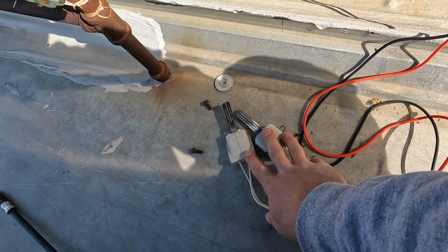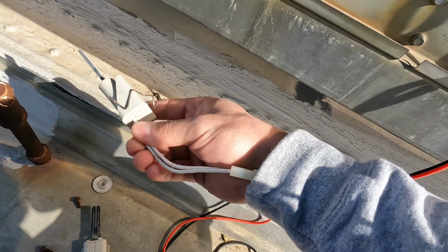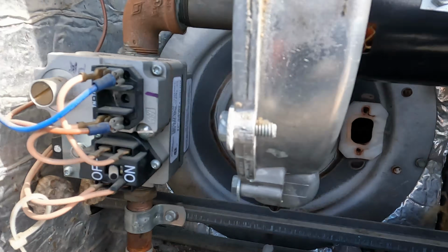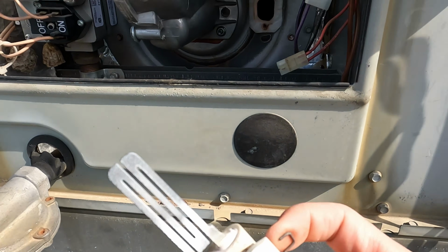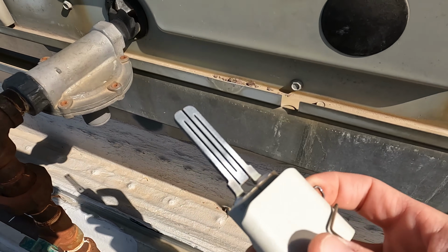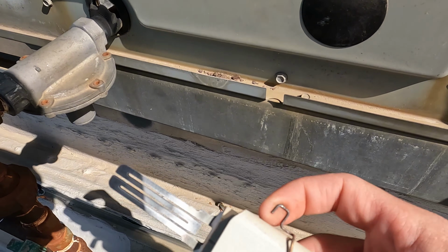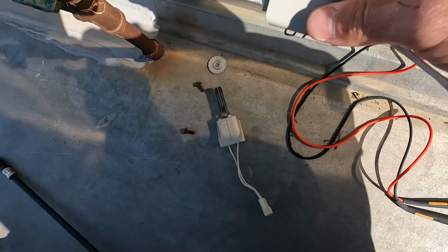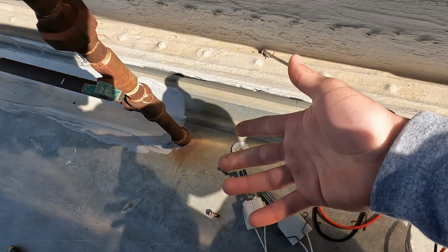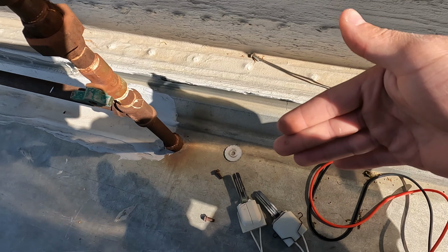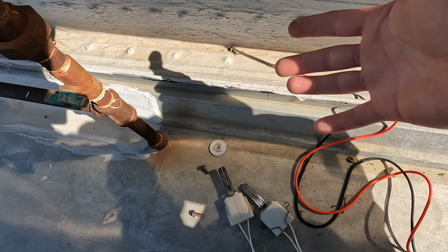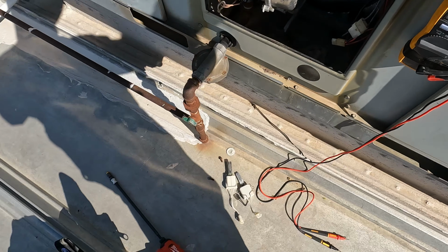So with both of these testing good, they also act as flame rectification. As you can see, there's no flame sensor in here. So with them being dirty, I guess technically it would make sense if it ignited just fine, because it's testing fine. But since they're dirty, the flame could cut out due to that. That's probably why he kept having them changed out.